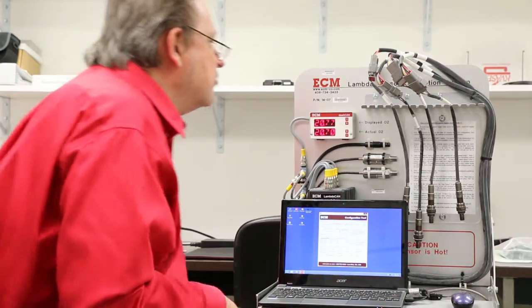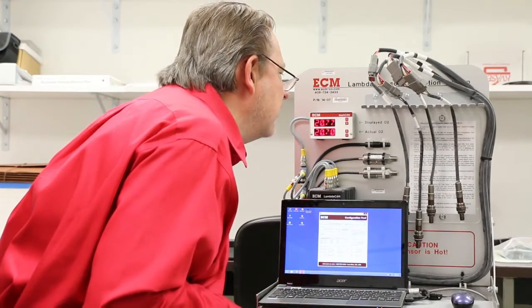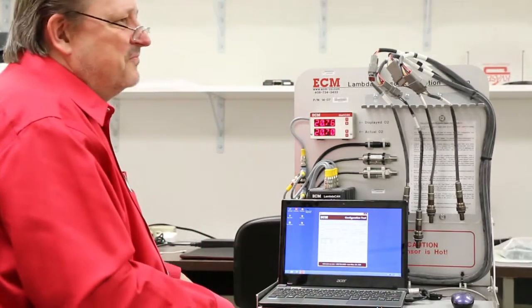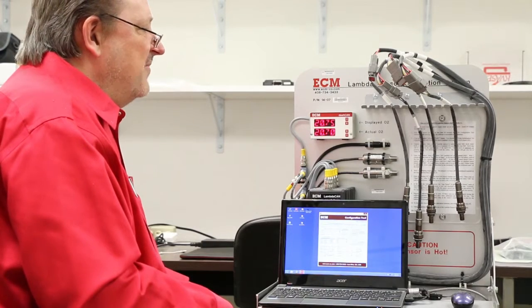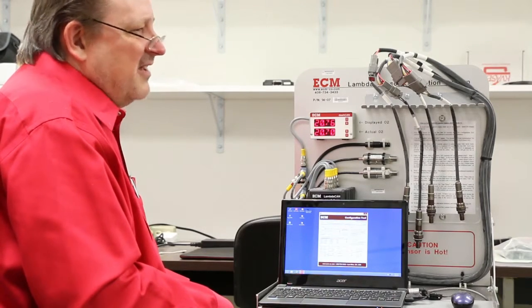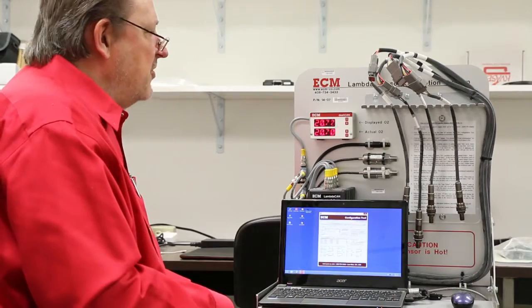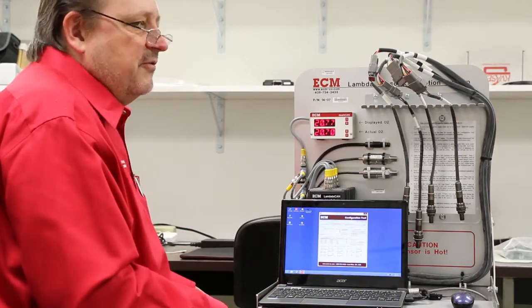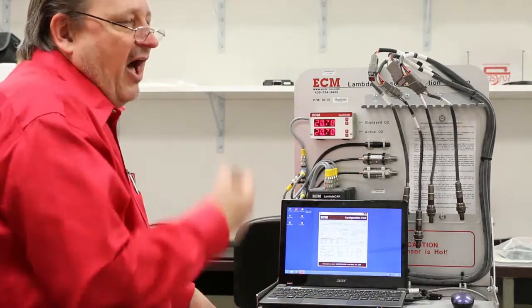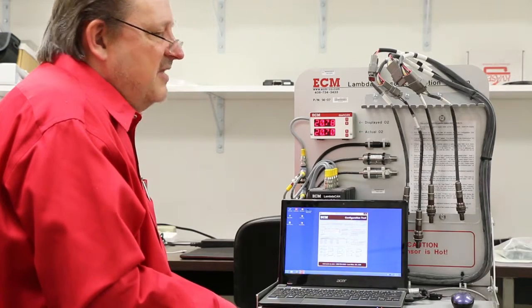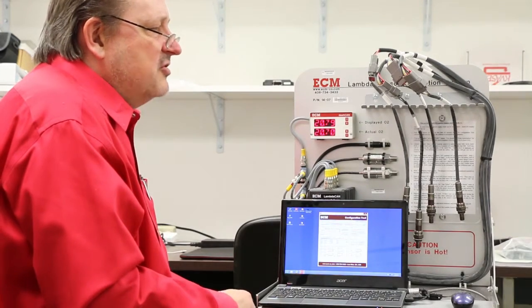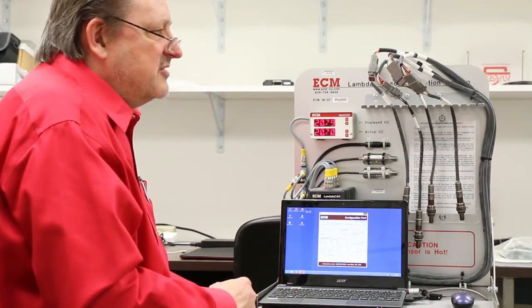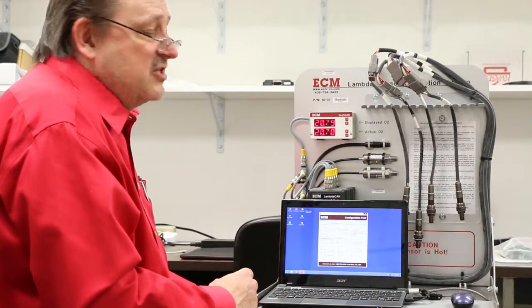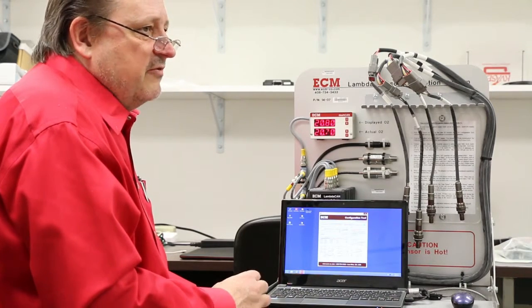When it gets down to about 0.8, the sensor's kind of ready to sign off. Although you can calibrate it and use it theoretically until it goes down to 0.5, it means the sensor's getting near end of life. So if you're going to have a long-term test or something, and you're not going to see a sensor for a while, it's best just to retire the sensor.